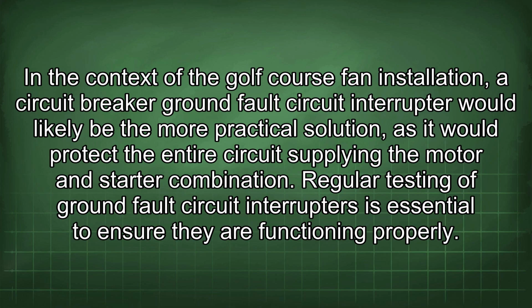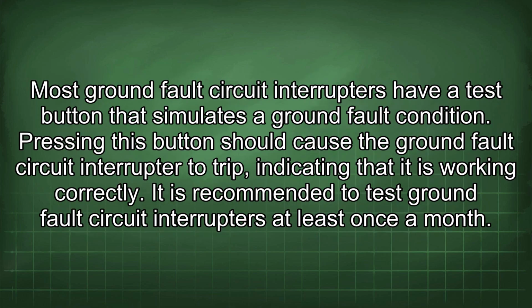Regular testing of ground fault circuit interrupters is essential to ensure they are functioning properly. Most ground fault circuit interrupters have a test button that simulates a ground fault condition. Pressing this button should cause the ground fault circuit interrupter to trip, indicating that it is working correctly. It is recommended to test ground fault circuit interrupters at least once a month.